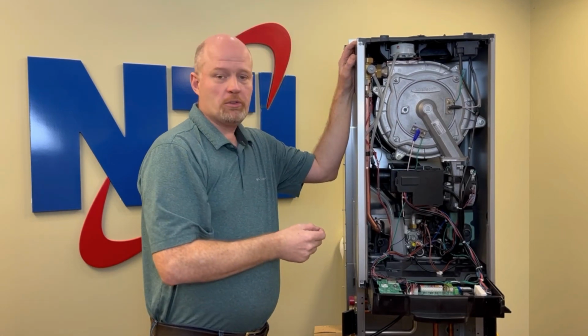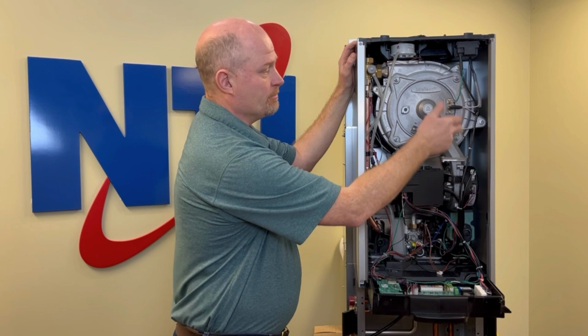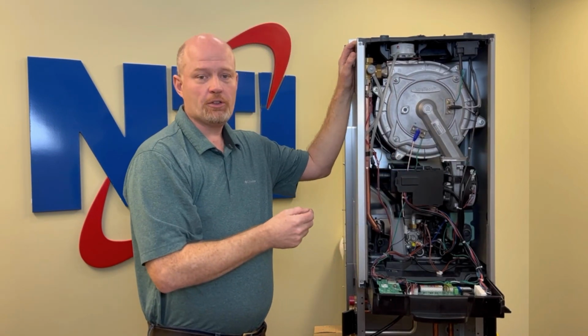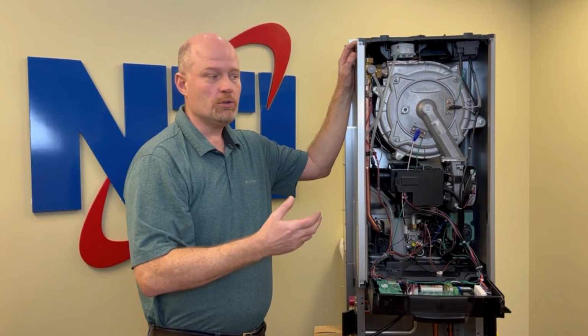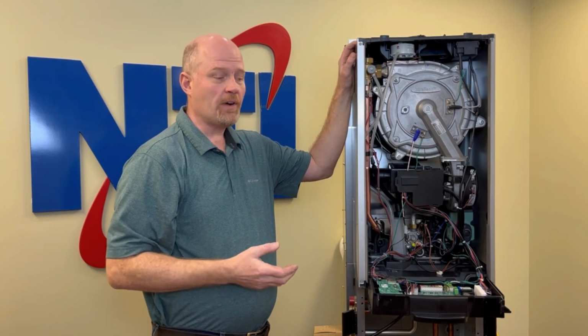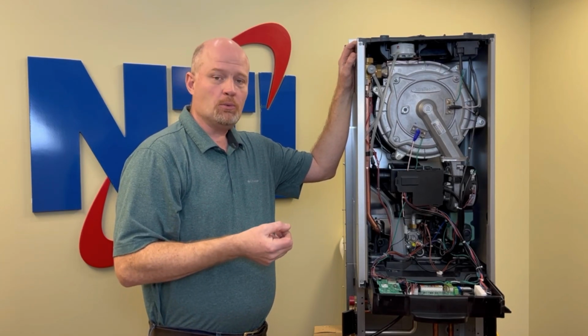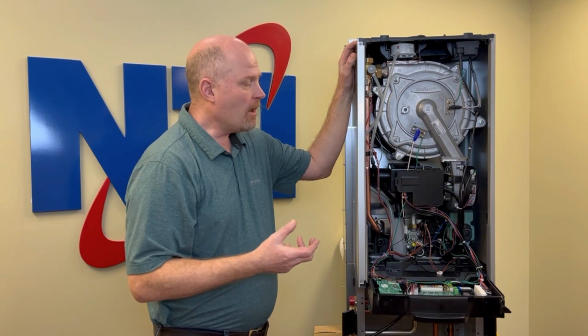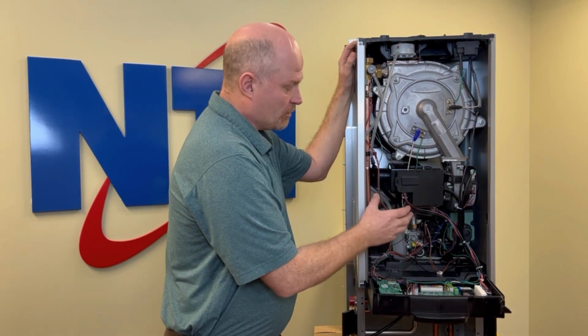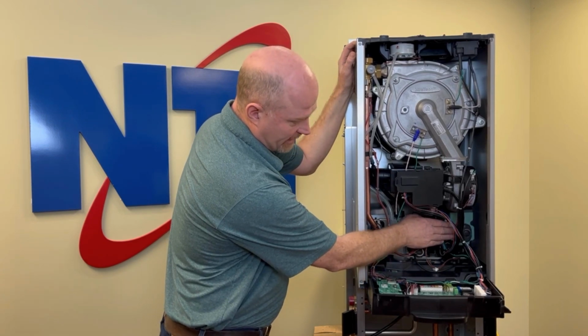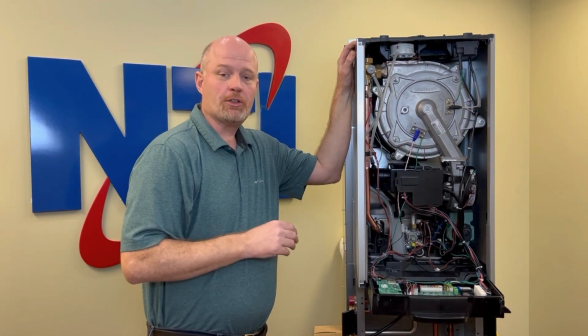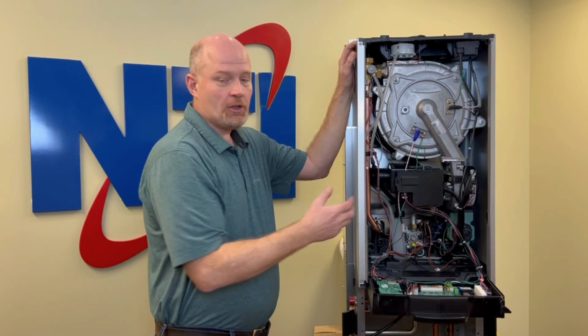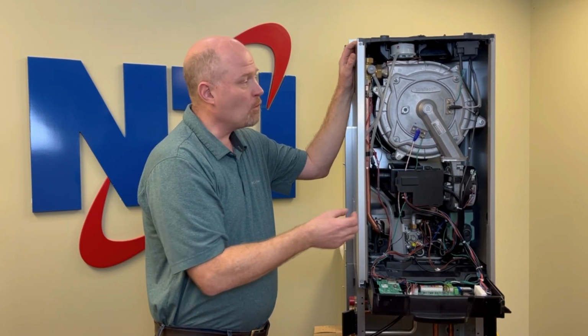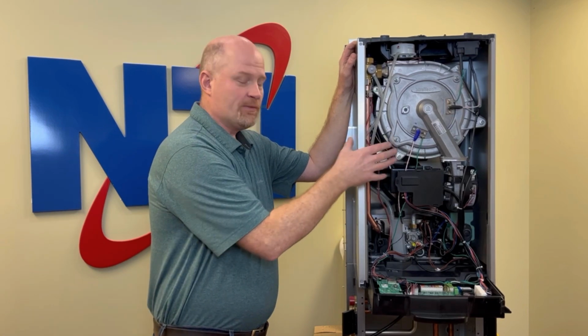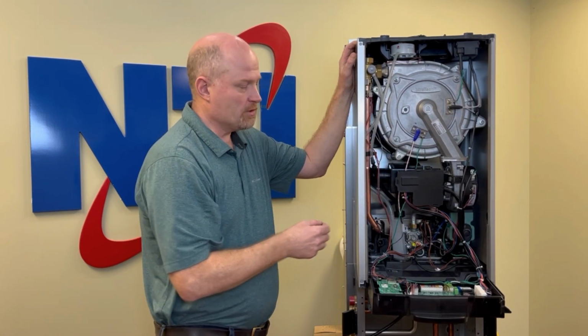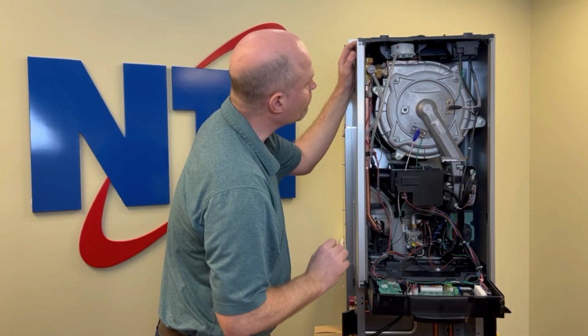Another cause of error code 602 could be air in the system. If you've got air in the system, you'll likely also get error codes 101, 102, 103, 4, or 5, and possibly 1P2, 1P1, and 1P3. All of these codes could indicate overheating of the boiler, so it's very important to make sure that your boiler is air-free, that you can see the blue light on the circulator turning on, and to verify that you have water flow. If you don't have flow or you have a boiler full of air, it is very likely that you will see 602 error codes, so you want to ensure that as well.